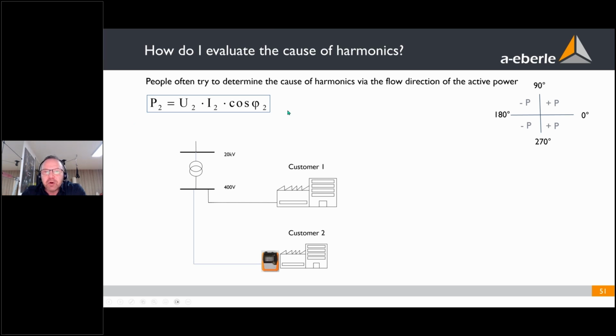So, like at 50 Hertz, we can calculate the power, with positive or negative sign, out of voltage multiplied with current multiplied with the cosine of the angle phi of this frequency. So we can do this with 50 Hertz, and we can calculate this also maybe for 100 Hertz. So the power of the second harmonic is the voltage of the second harmonic multiplied with the current of the second harmonic multiplied with the cosine of the angle of the second harmonic. So an analyzer can calculate all of this.